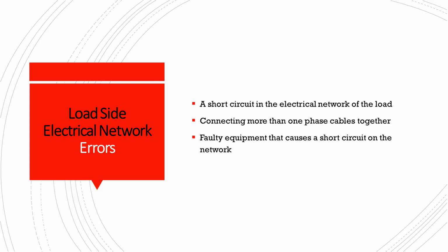We discovered that there's something wrong with the blue phase of their system. So we now ran just those 2 phases for a long time, and we discovered that these inverters were no longer shutting down. So we now discovered that probably there is a short circuit along the blue phase of the line that we are supplying to the load.